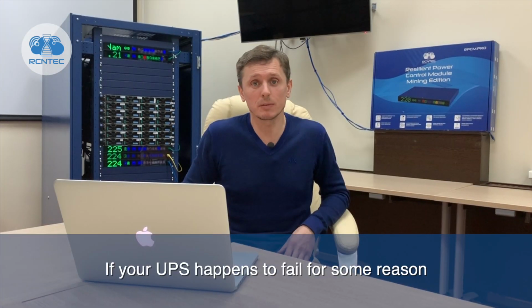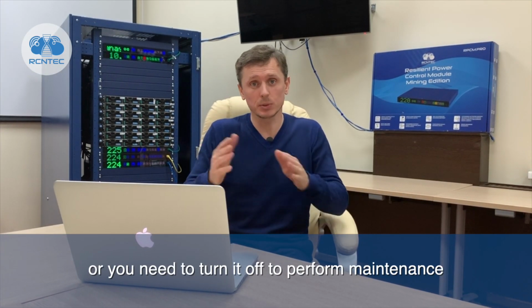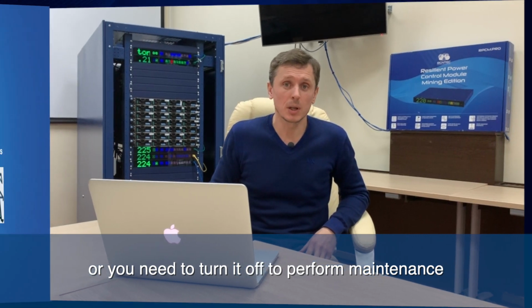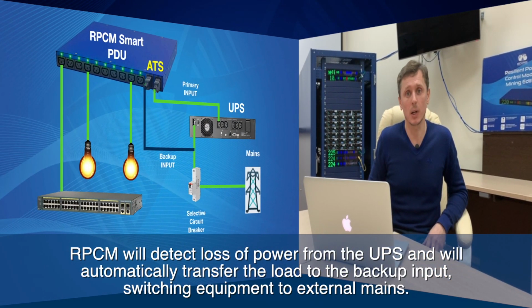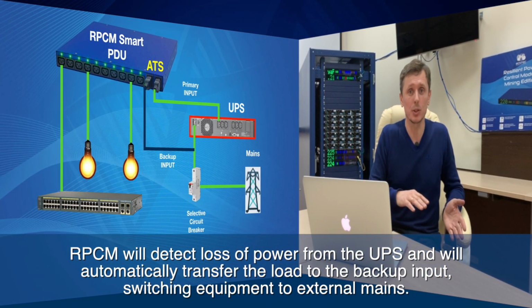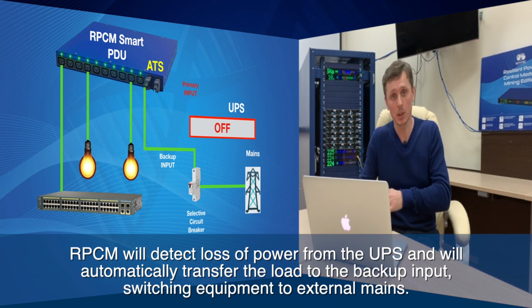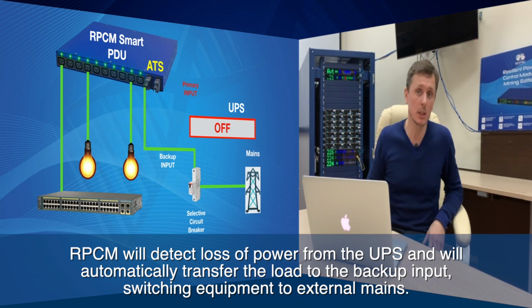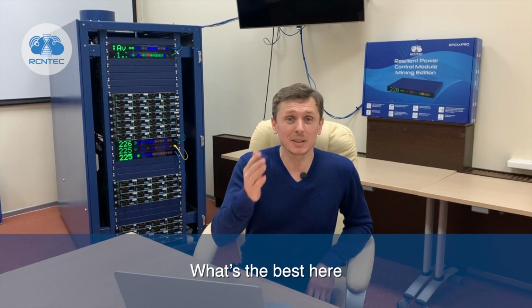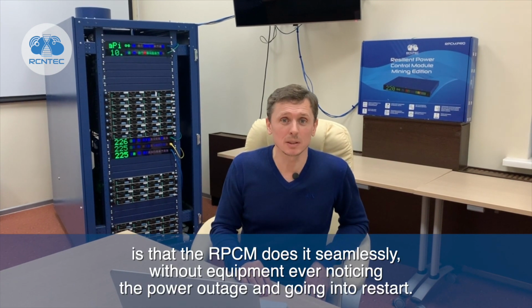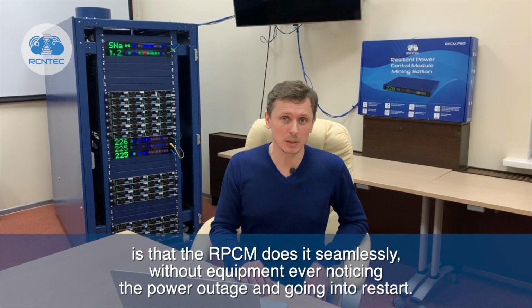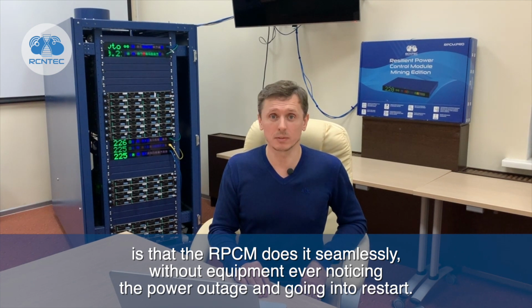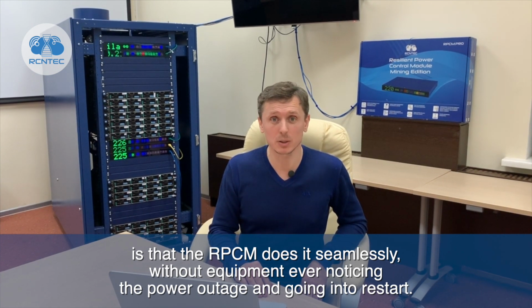If your UPS happens to fail for some reason, or you need to turn it off to perform maintenance, RPCM will detect loss of power from the UPS and will automatically transfer the load to the backup input, switching equipment to external mains. What's the best here is that the RPCM does it seamlessly, without equipment ever noticing the power outage and going into restart.